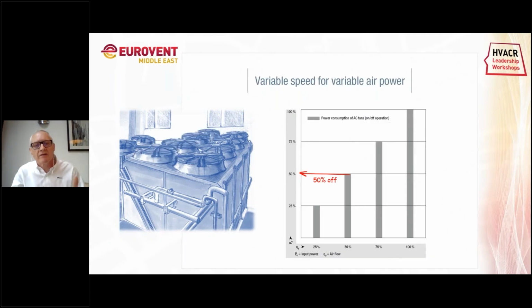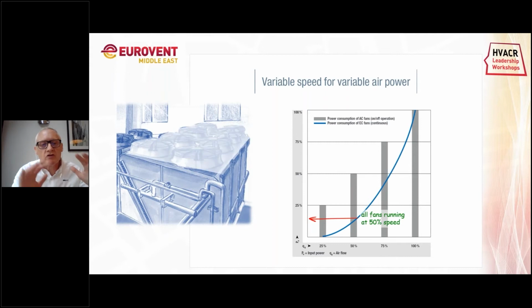Okay, so if you only need 50% of the air volume, so on and off, we were talking earlier about on and off. If you do that on and off, you're going to reduce the actual power consumed by 50%, as you can see in the graph illustrated on the right-hand side. With an EC fan, what we do is we reduce all 8 fans to 50% of their running speed. By doing that, we consume 80% less energy. So that's a terrific saving. So we always do that.